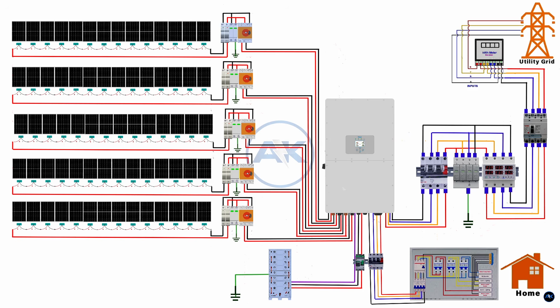Step 7. Current Transformer or CT Clamp. Now we install the Current Transformer or CT Clamp. This component is what enables zero grid export. The CT clamp measures how much power is flowing between the grid and the building. The inverter uses this information to make sure no electricity is sent back to the utility grid. The CT must be installed on the main grid supply cable before the inverter connection and after the utility meter. This position allows the inverter to see the total power flow of the site.